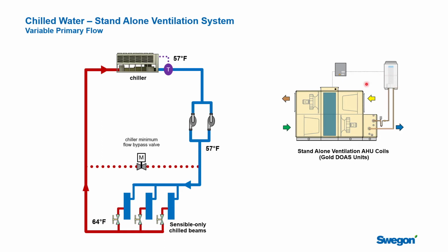So as soon as it starts to cool off outside, you're going to see a big improvement on the COP. And this system is not likely to run once the dew point of the air has been met, which is somewhere around 56 degrees. So once you get to that temperature, you're going to shut down your refrigeration system and just use the outside air. It might run in heat pump mode, but it's probably not likely to happen.